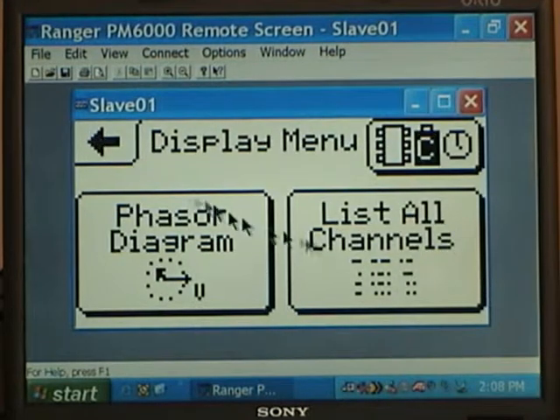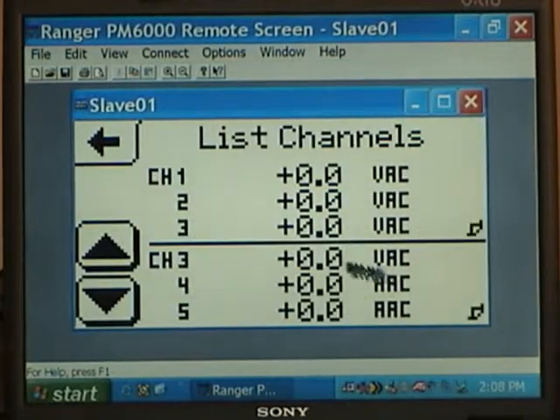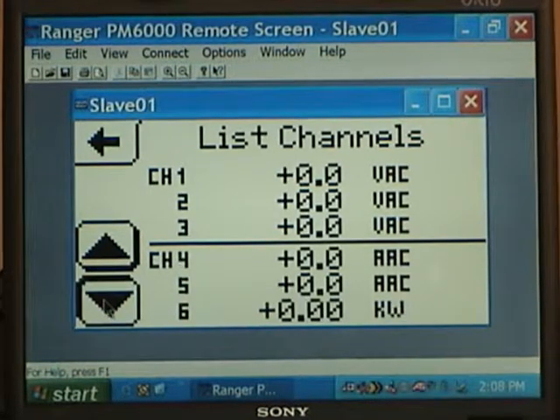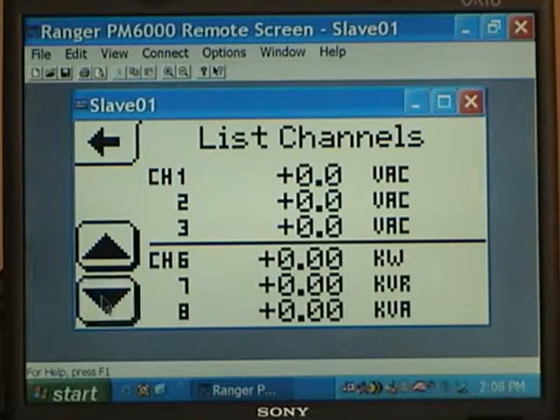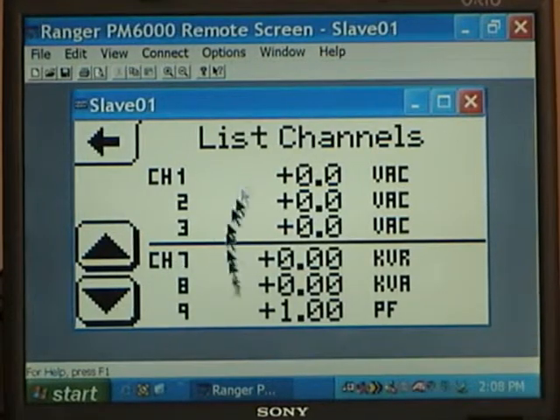Going back with the upper left-hand corner, we go to a list of all channels. I'm showing channel 1, 2, and 3 in the top half of the display, and channel 3, 4, and 5 in the bottom half of the display. If I want to see channel 4, 5, and 6, I can see my two currents, L1, L2, and the beginning of my power channels, which would be kW. If I continue to scroll down here, I have kVAR, kVA, power factor, and so on. You're able to display whatever you want, wherever you want.